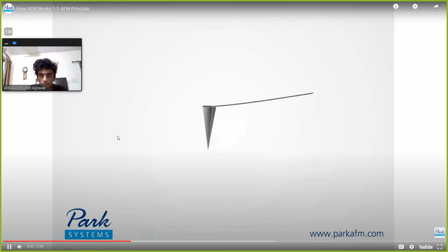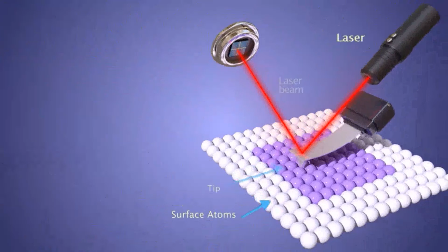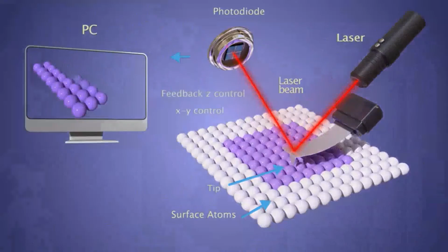This is a cantilever beam. As the tip approaches the surface, AFM principle: surface sensing. An AFM uses a cantilever with a very sharp tip to scan over a sample surface. As the tip scans, it moves up and down to follow the contours of the surface of nanostructures, and the cantilever is deflected accordingly. The magnitude of this very minute deflection is then recorded by the position of the reflected laser beam in the position detector. Our software lets us see.